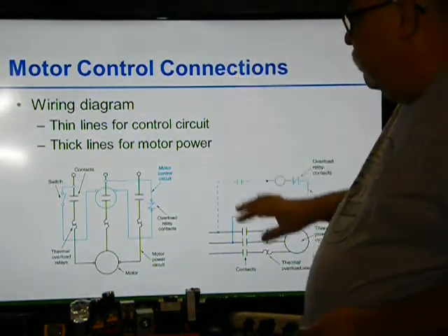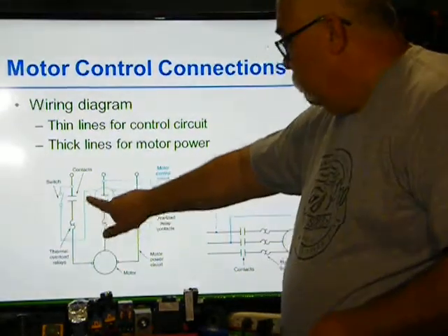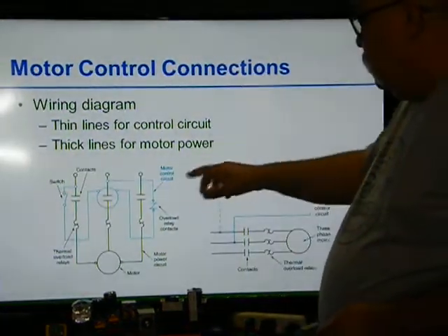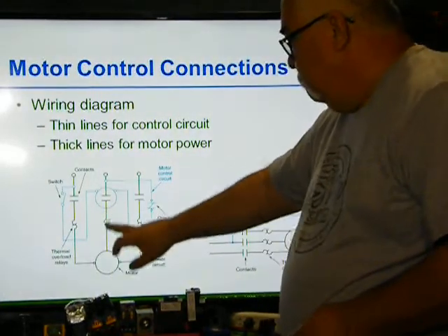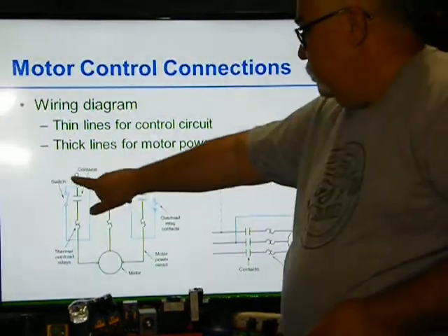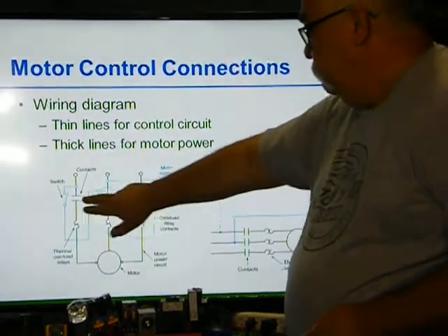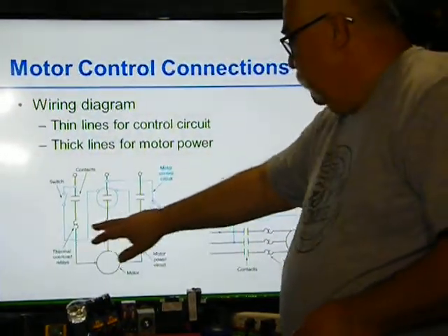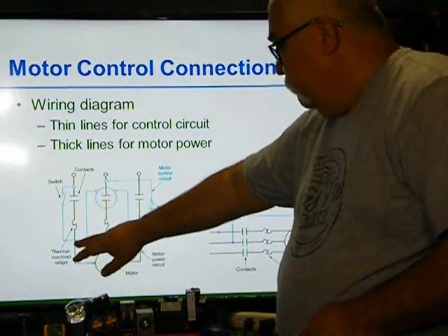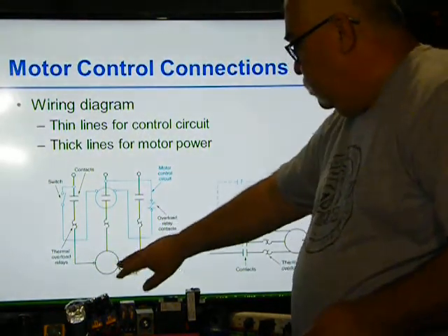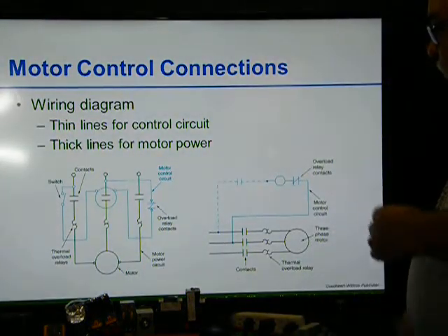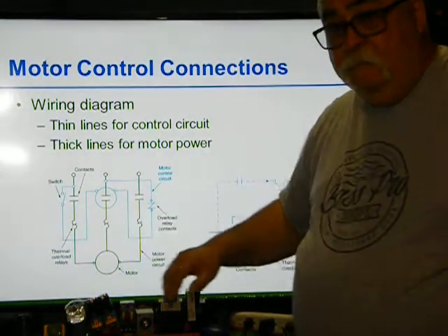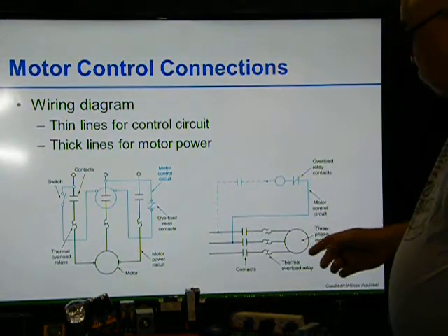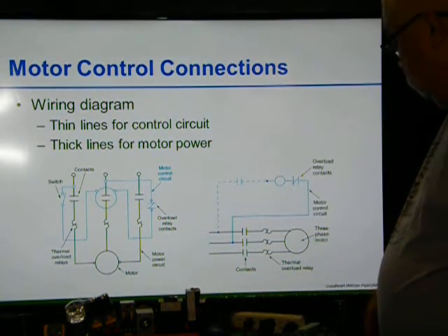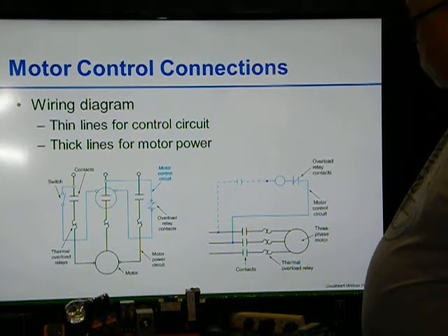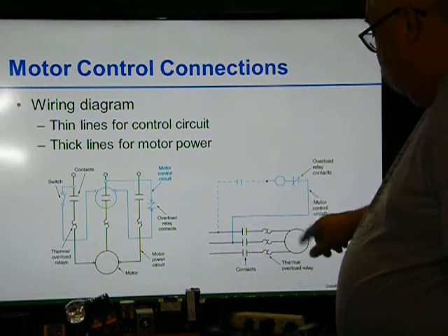So in the wire diagram, our thin lines, which are these blue ones, are our control circuit. The thick lines are the motor power. So here's my power coming in. This is my L1, L2, L3, contacts, my overloads, and then coming off the overloads would be T1, T2, T3 going to the motor. This is a 3-wire control. This one here is a 2-wire control, so you only have one way to turn it on. Whatever this closes, it turns everything on.